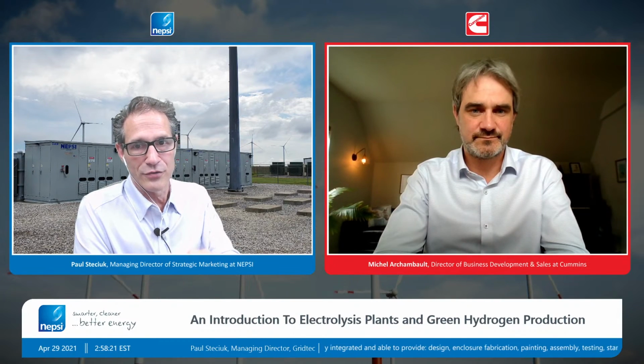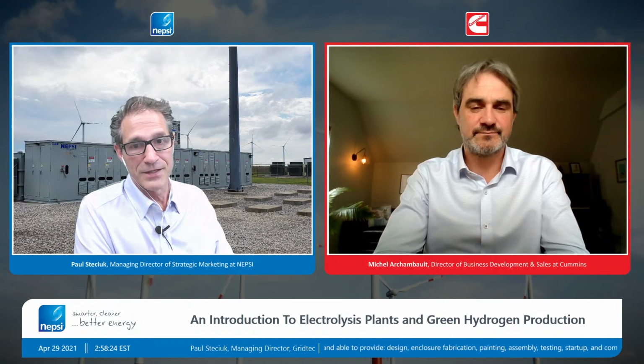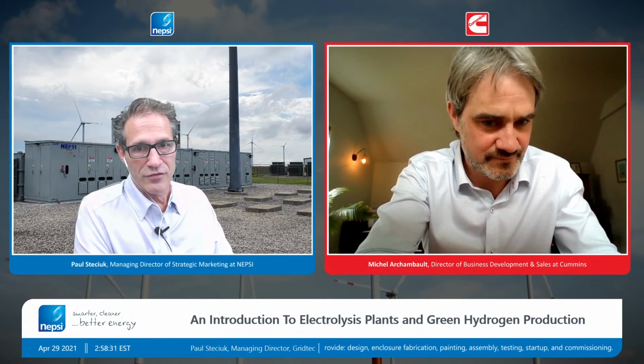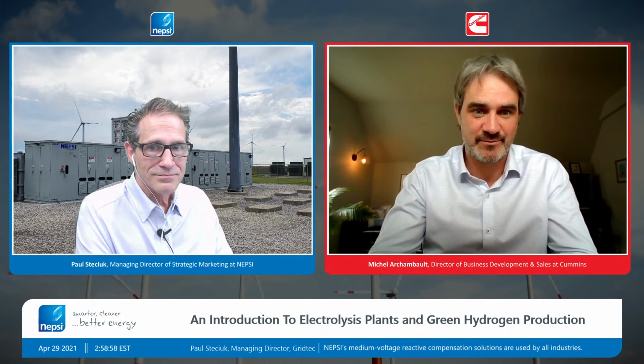Matthew asked: any idea how many megawatt hours of power generation 1 ton of hydrogen can fuel with modern day CT heat rates? I can give you the HHV, the higher heating value of hydrogen, which is 39 kilowatt hours per kilogram, not to the decimal. So a ton would be 39,000 kilowatt hours, or 39 megawatt hours per ton.